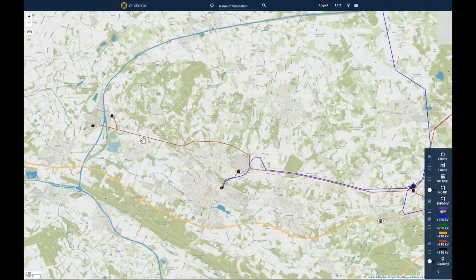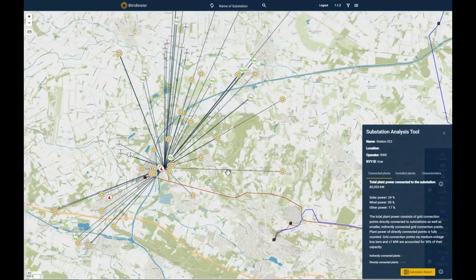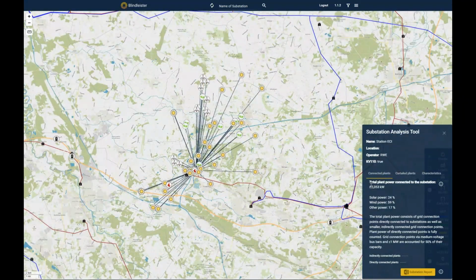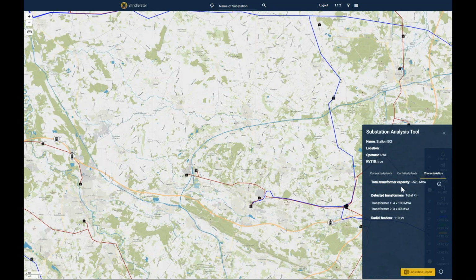So we are focusing now on this area. We want to connect to this substation here, Station ECI. We check what's happening here. We see there is like around 60 megawatt connected. Solar power is connected, wind power is connected, and we have a bunch of transformers because that's also a load center here. We see what kind of transformers.